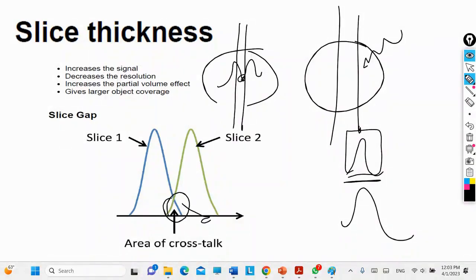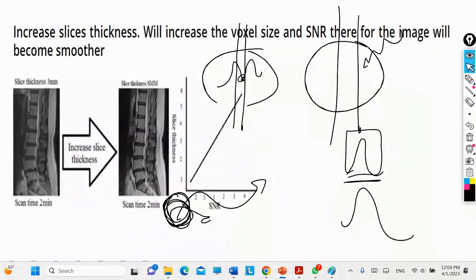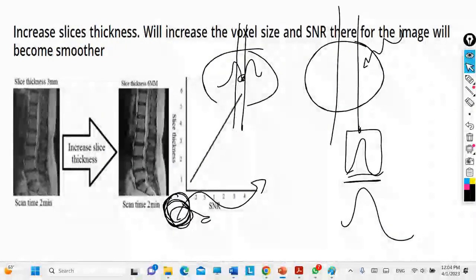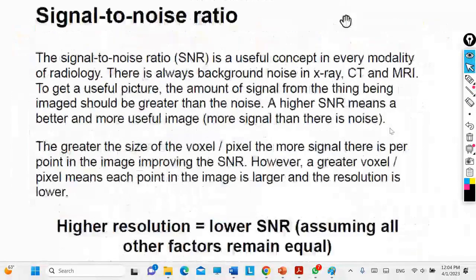When you come to the second slice, the overlapping part that was affected by the first slice is already very weak. It didn't recover fully. So when you apply your RF pulse to the second slice, that region is already weak, and consequently it gives you a signal that is very weak compared to the rest of the signal.